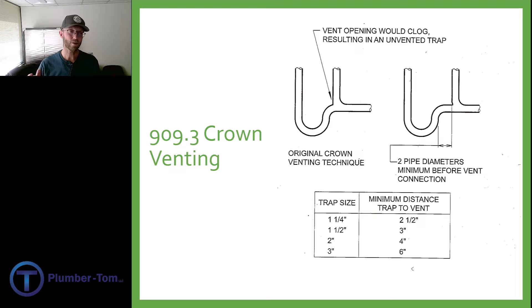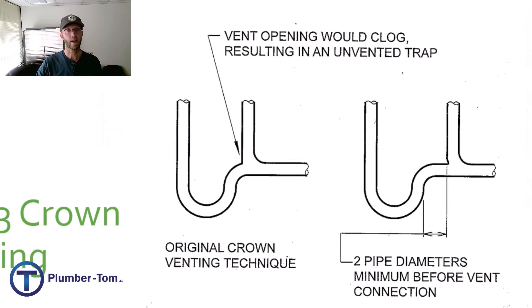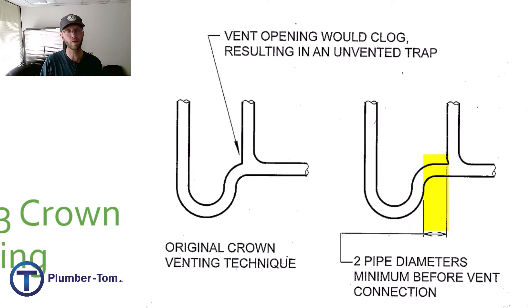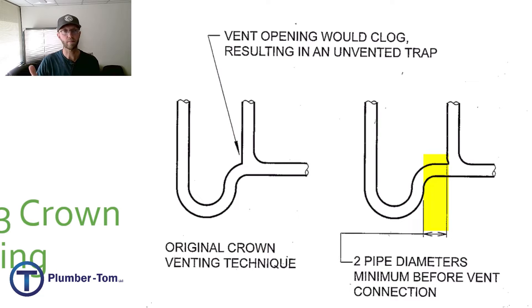Section 909.3 talks about crown venting. A crown vent is when you have a vent that comes right after the trap. If it's too close to the trap, that vent can actually get plugged by the fluids and material coming through the drain. For that reason, when we're crown venting — and it is still allowed — you have to be two times the pipe diameter downstream. That's still not very far: if you have an inch-and-a-half trap, that's only three inches downstream. This applies any time you're hooking up a trap in a cabinet under the sink — maybe you're going to do an auto vent. Make sure that you're downstream far enough for those vent connections.